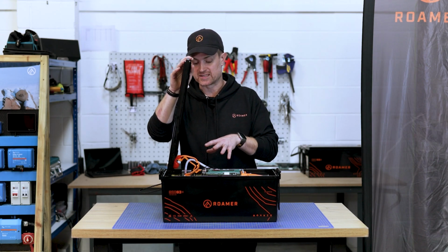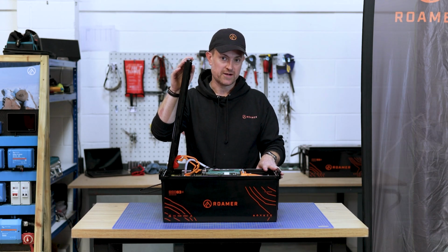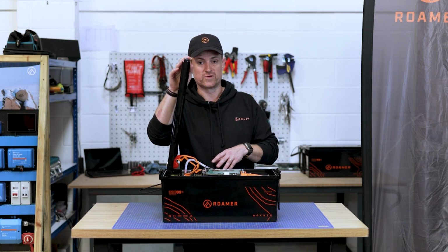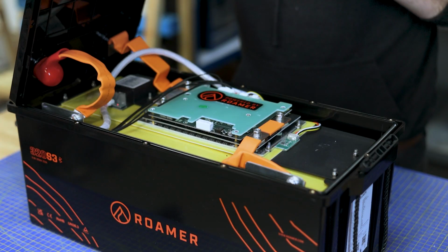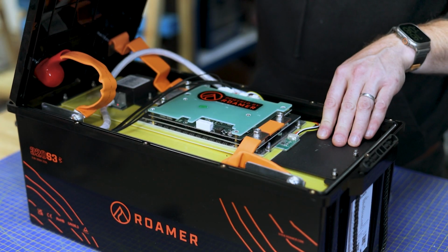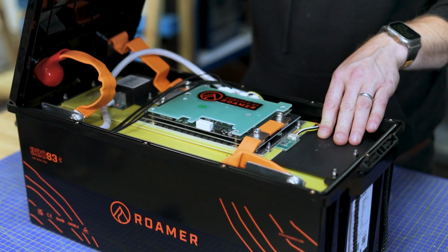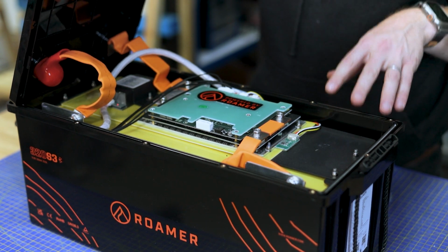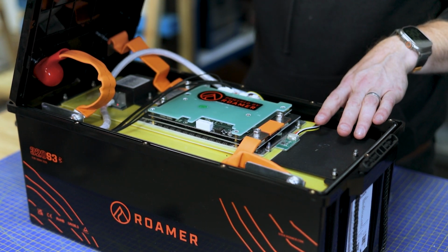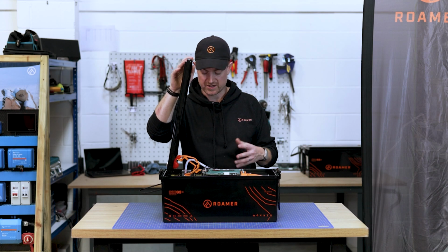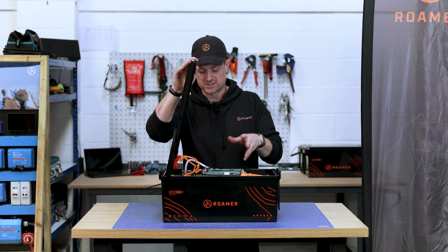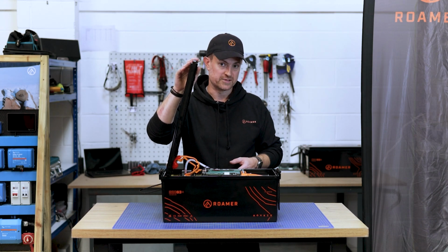The reason we add the active balancer, you may not notice straight away, but throughout the course of a battery's life, we're trying to maintain that it lasts as long as possible, getting the most cycles and usable capacity. The power draw of the active balancer is actually very low, about 7.2 watt hours per month. That's pretty negligible - you're basically increasing the self-discharge rate from 3% to 4%, so it's negligible.